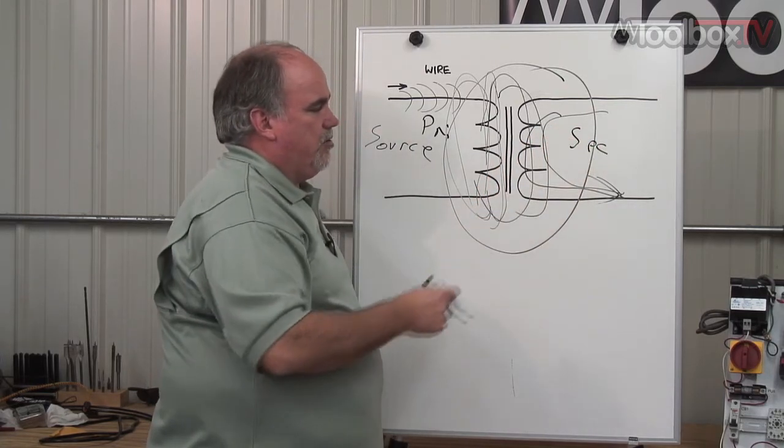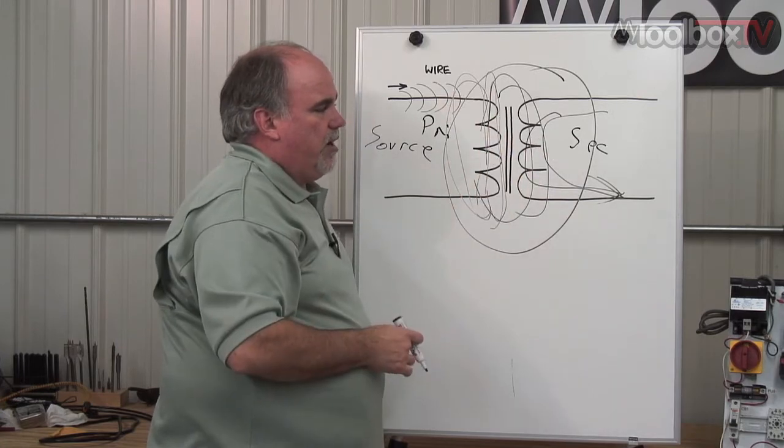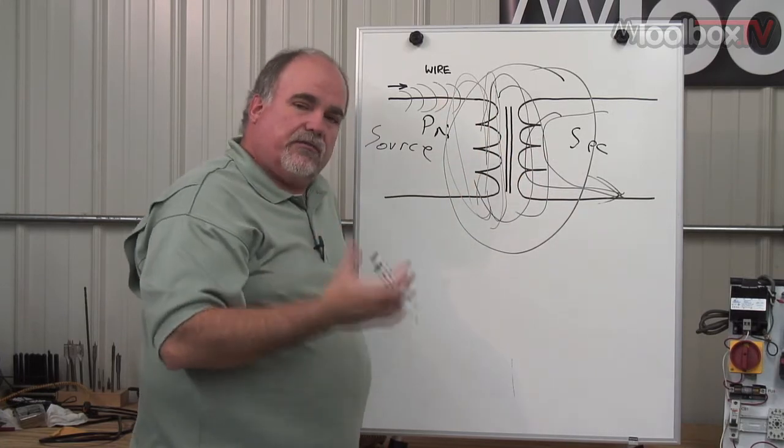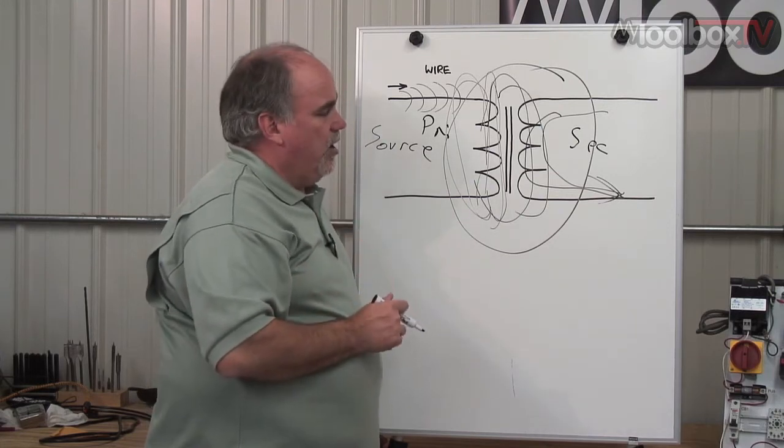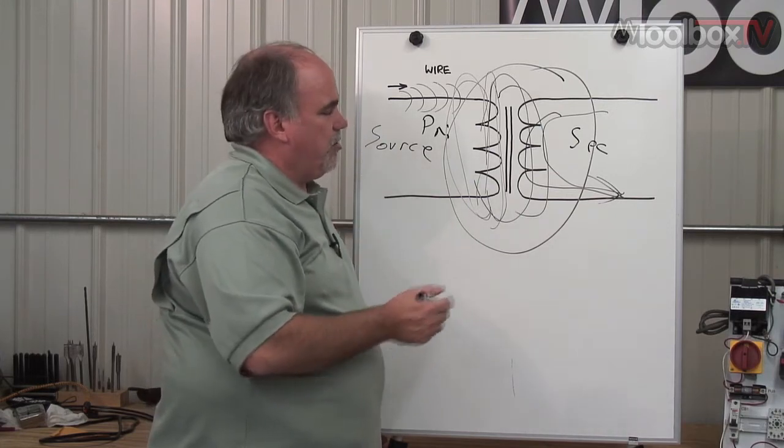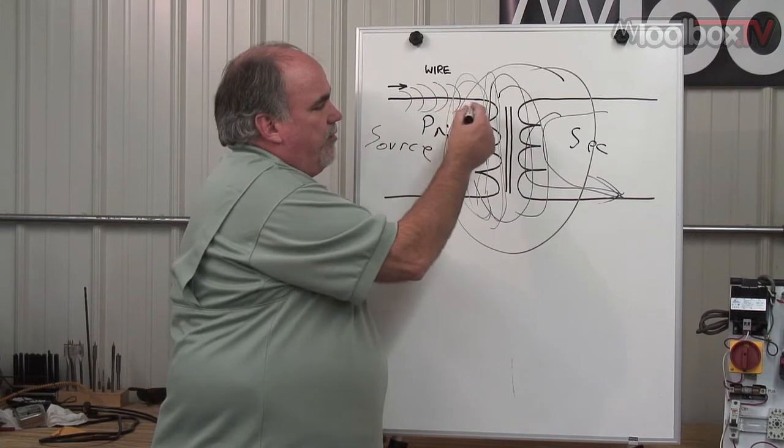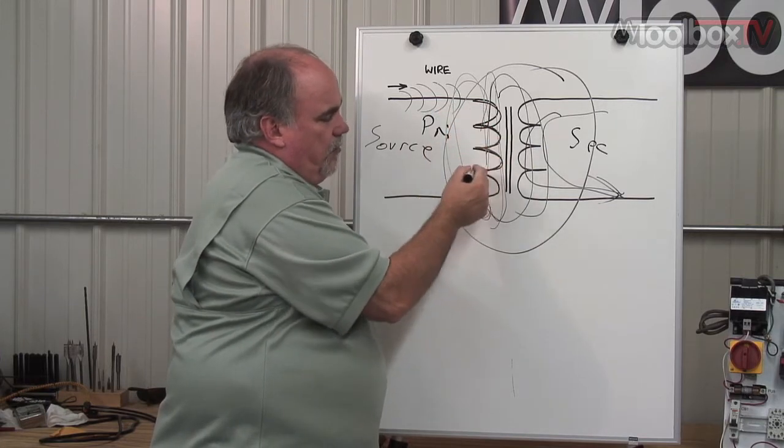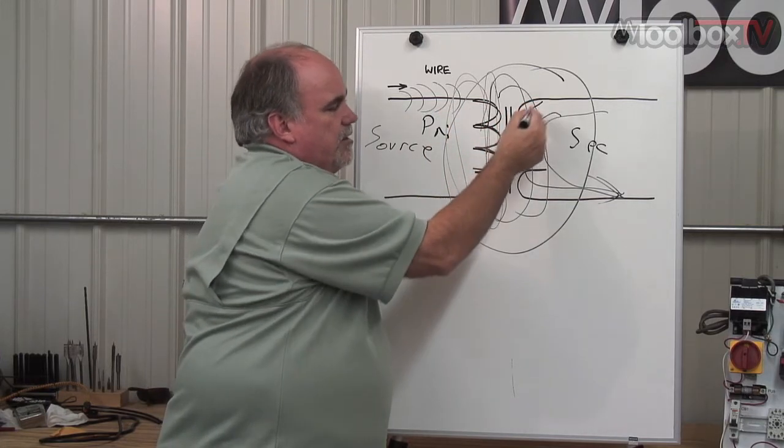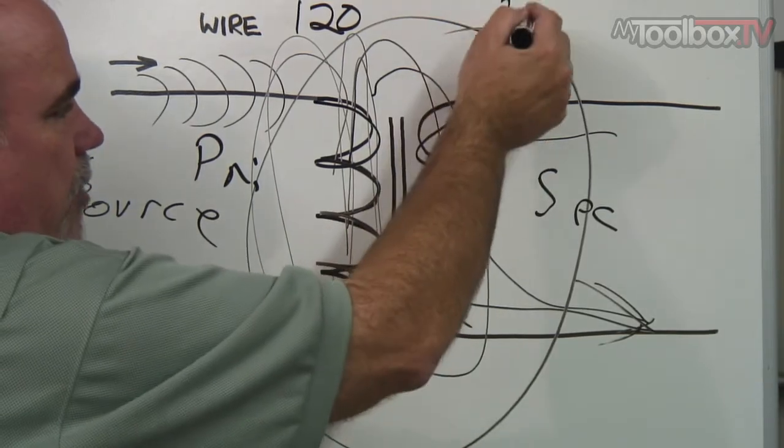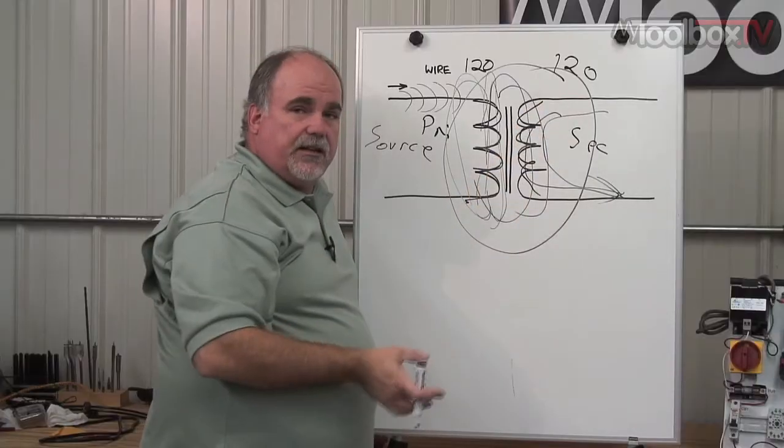That's the side that you can use a transformer to do things like change the voltage. If it's an isolation transformer, it means you're not changing the voltage. That would mean that the number of turns of wire on this side is the same on the secondary. So if you had 120 volts on the primary, you'd have 120 volts on the secondary.